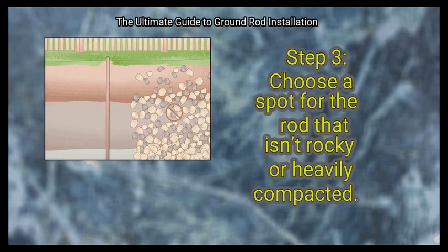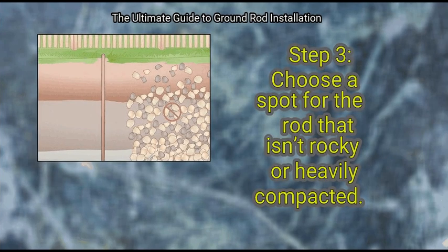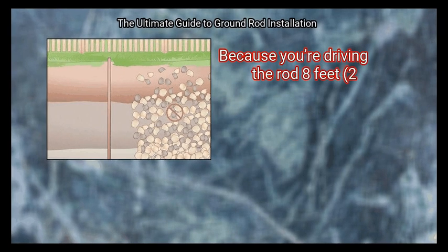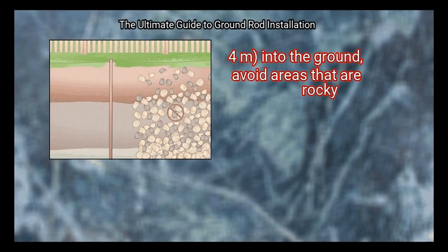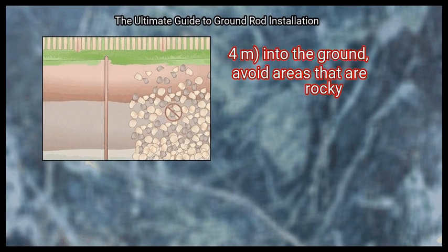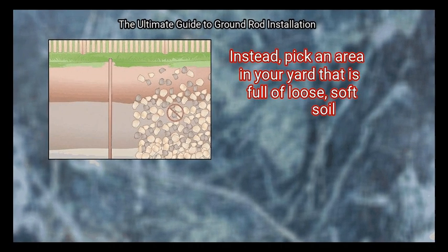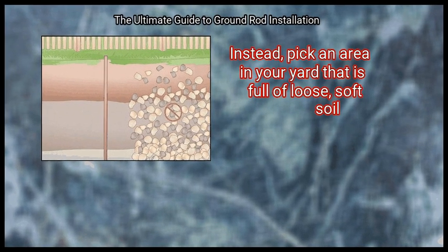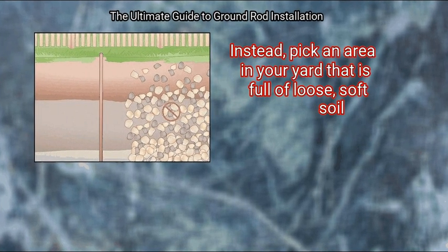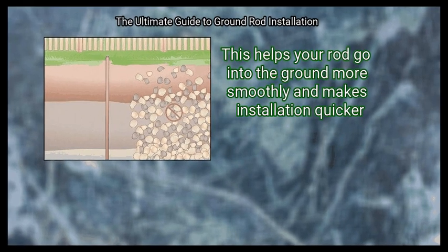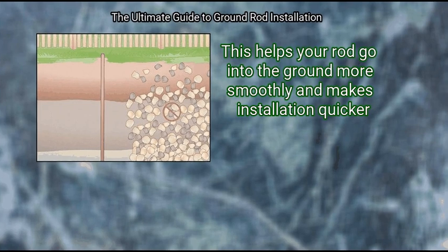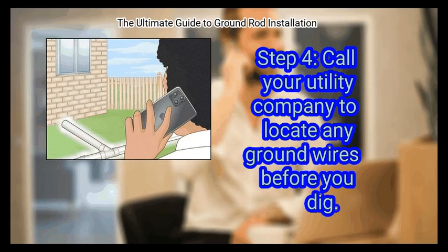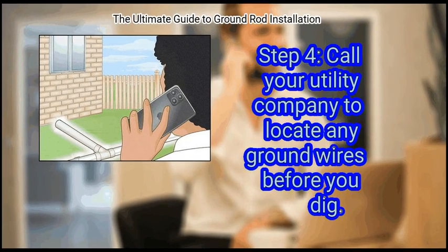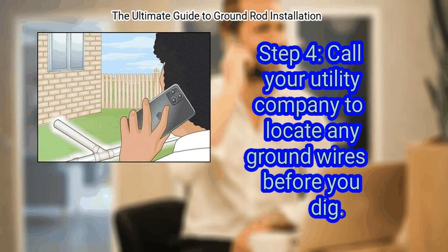Step 3. Choose a spot for the rod that isn't rocky or heavily compacted. Because you're driving the rod 8 feet, 2.4 meters into the ground, avoid areas that are rocky. Instead, pick an area in your yard that is full of loose, soft soil. This helps your rod go into the ground more smoothly and makes installation quicker. Finally, call your utility company to locate any ground wires before you dig.